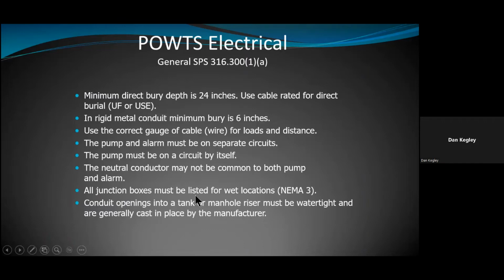All junction boxes must be listed for wet locations. NEMA 3 is the minimum here. I've noticed in like the Zoeller and some of the other ones, they basically are putting in a NEMA 4 enclosure. And basically the difference is a NEMA 3 is just a rain tight enclosure. So it basically will keep the rain out of it kind of thing. Where a NEMA 4 enclosure is more of a dust tight enclosure.